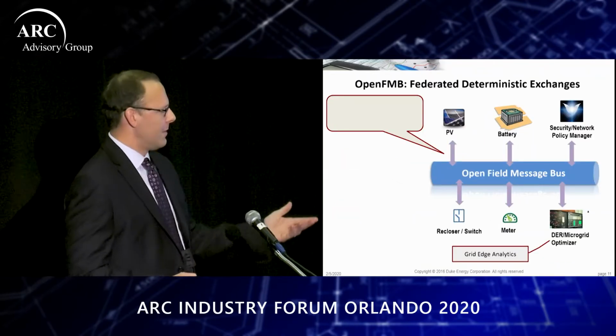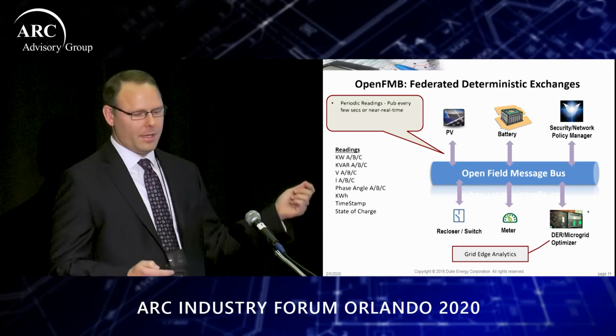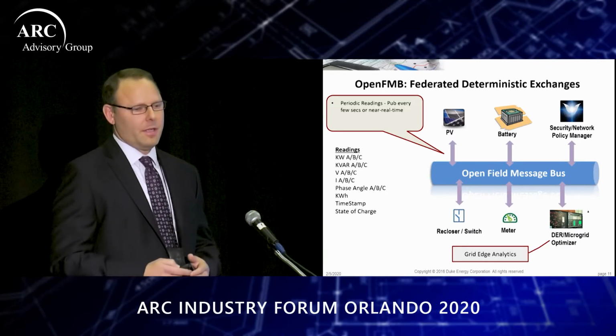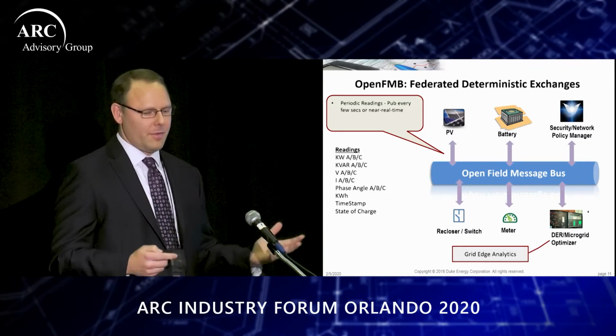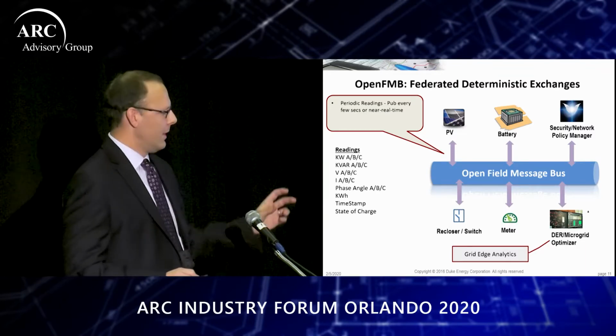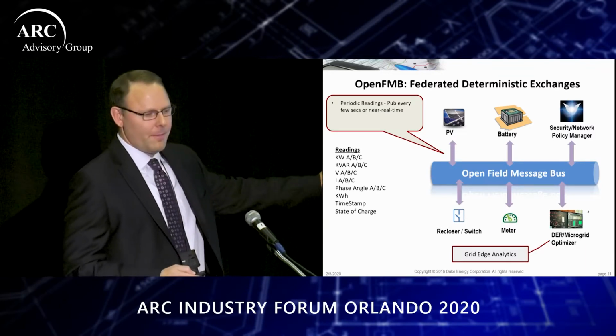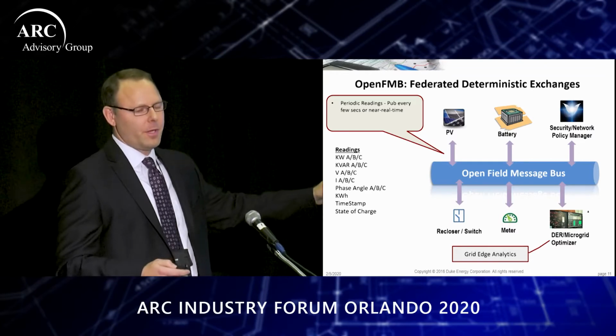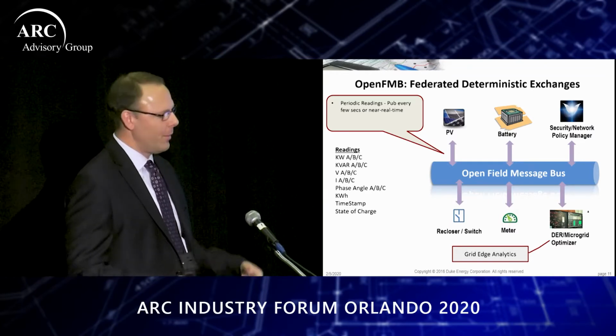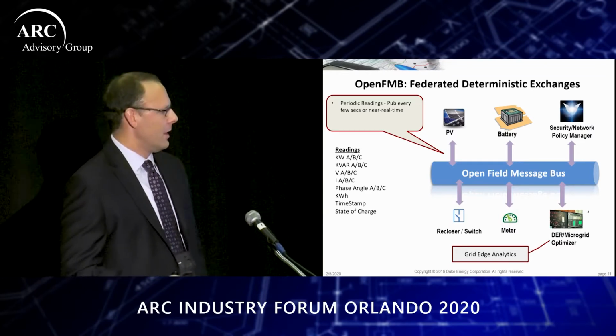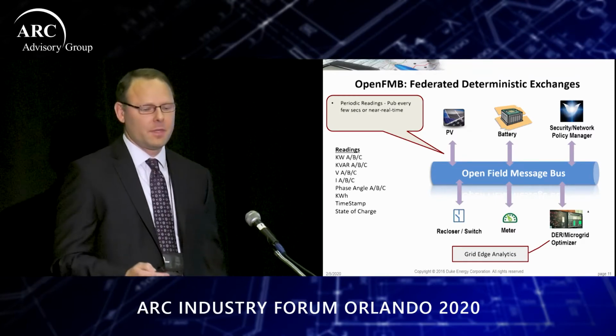On this message bus, you have to define the payload. It's a standard definition based on the common information model or 61850, and you can federate and segment each into what we call a profile. For example, one profile might be a reading, essentially the monitoring measurement data.